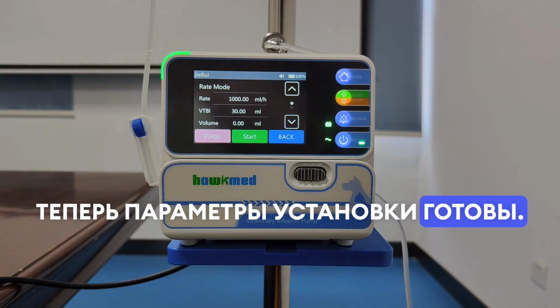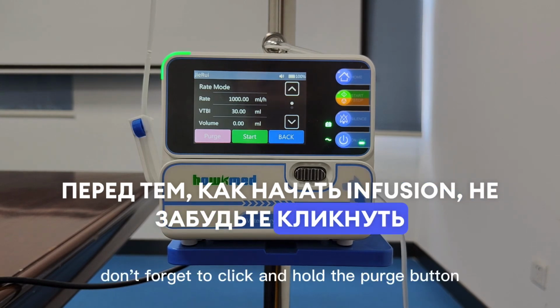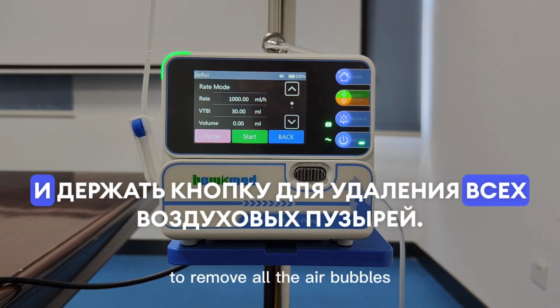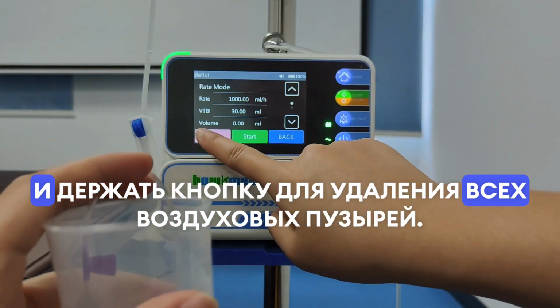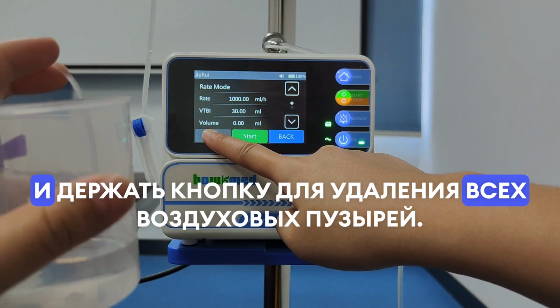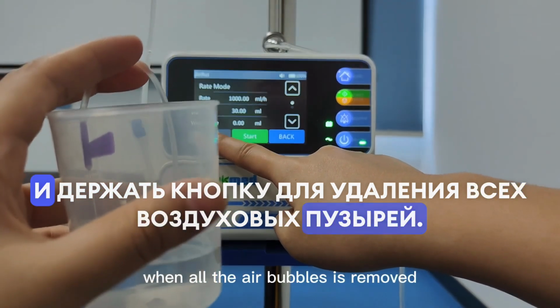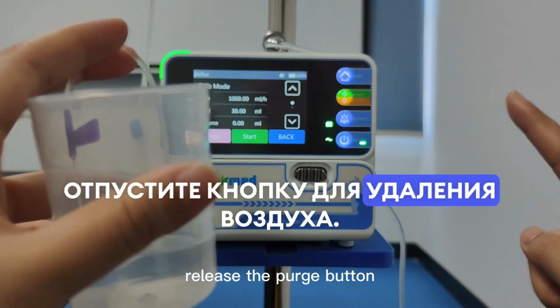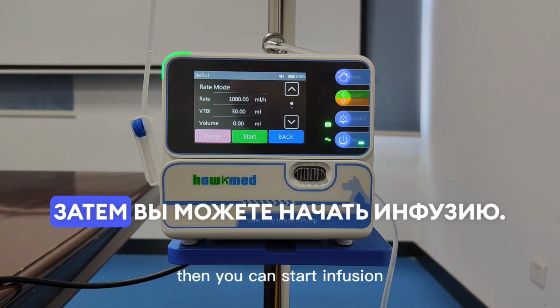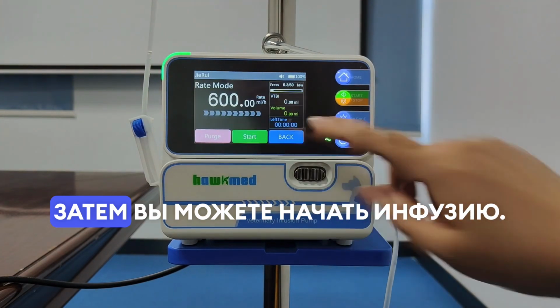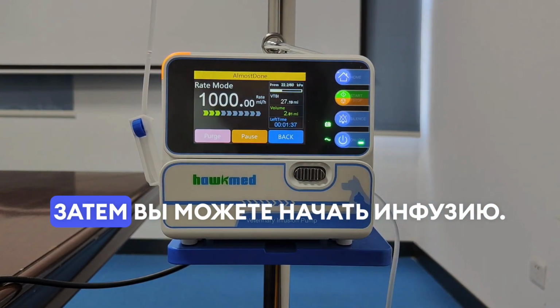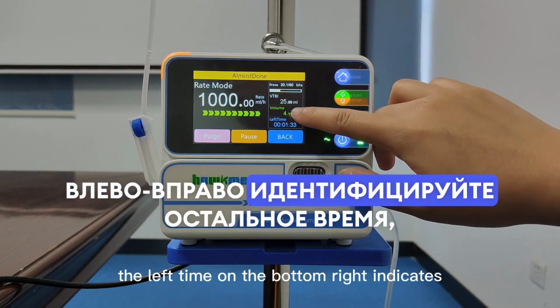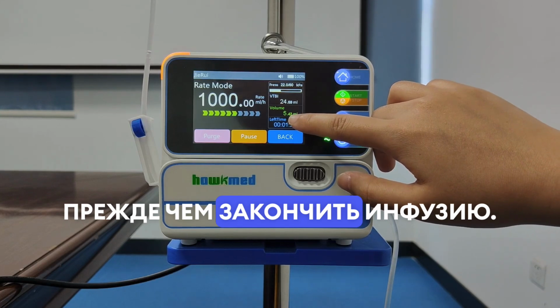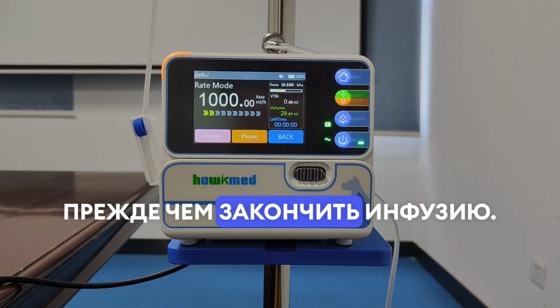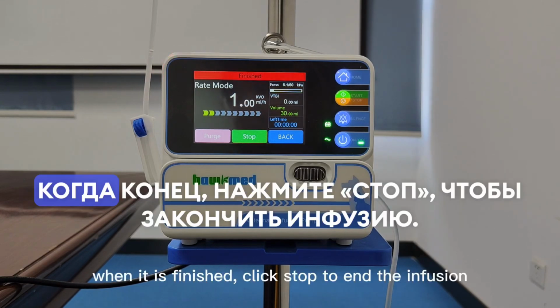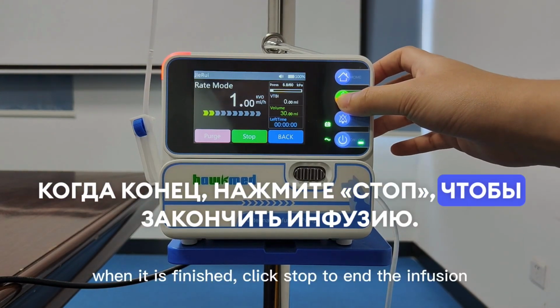Before you start infusion, don't forget to click and hold the purge button to remove all the air bubbles. When all the air bubbles are removed, release the purge button. Then you can start infusion. The time left on the bottom right indicates the time left before the infusion ends. When it is finished, click Stop to end the infusion.